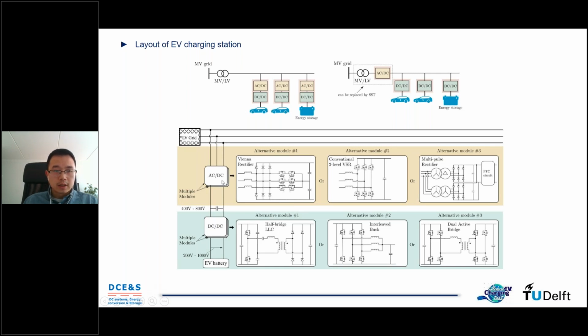Usually they use a modular design, meaning you may have several sub-modules in parallel to handle big currents. The topology of the sub-module could be a Vienna rectifier, which is very widely used. It could also be a two-level rectifier, or in some cases, if you want to save cost, you can go with a multipulse rectifier.